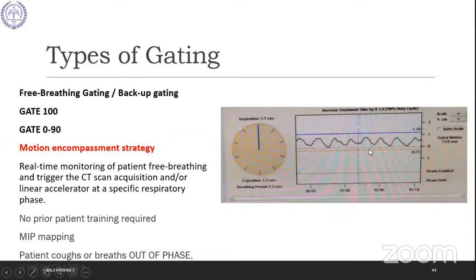So why do we employ this? One reason is to ensure that we use the MIP technique, and the MIP technique will work only if the patient breathes in the same pattern. So it's very important to monitor that. And when we monitor that, if the patient breathes out of phase or coughs, the beam will be switched off. So that's the advantage. It's basically a monitored, controlled radiotherapy where you have given a personalized ITV. That's essentially what backup gating or free breathing gating is.